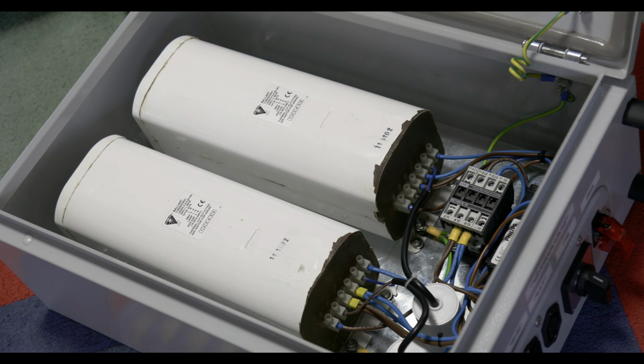Let's have a look. In a previous video I cobbled together this gearbox. It has two 1000 watt ballasts. Each one is designed to run a single 1000 watt high voltage metal halide lamp on ordinary 240 volt mains, but I can run them together in parallel to run a single 2 kilowatt lamp. Anyway, what's inside each ballast is basically just a step up transformer and then a normal high voltage choke. Because the chokes are not auto transformers, you can run them in parallel and they work quite well that way. Obviously it's not ideal, but it works. So what I'm going to do in this case is use a variac to lower the input voltage to get the desired lamp current.